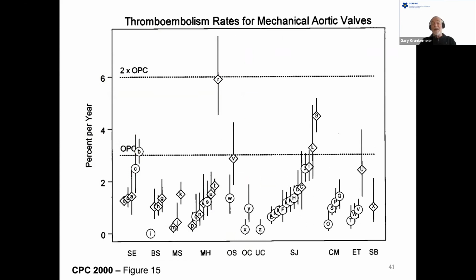This is the updated figure of the one I showed previously for thromboembolism rates in mechanical aortic valves, and this one has the OPC superimposed on it. You can see that although the pattern of results looks similar to the previous, they are lower than the OPC, way lower than 2 times the OPC. So a stricter, lower OPC was needed.